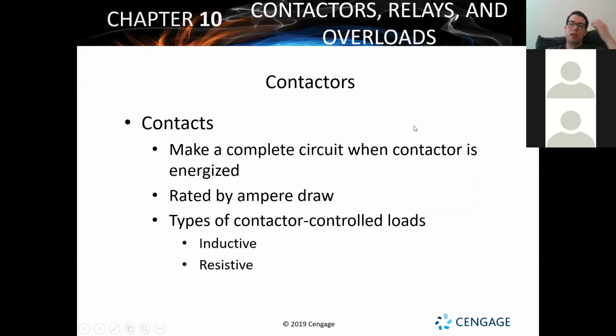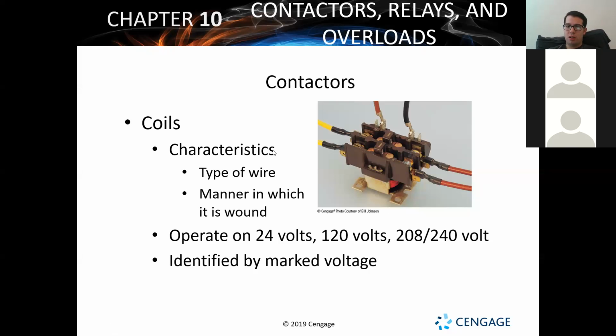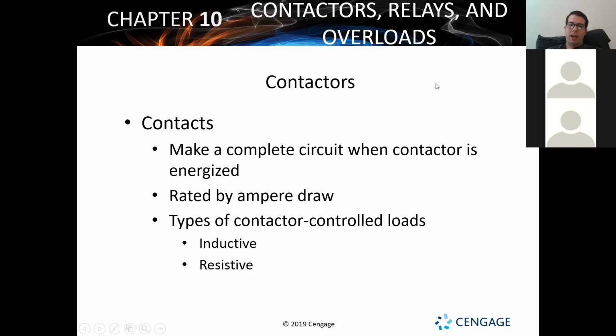So again, the contacts, that's what we were looking at right here on the ends of the contactor. You've got your contacts, and that's what's going to allow for power to be coming in and going out. Now, checking your voltage on your contacts is important. When it's an outdoor unit, you're going to have your power coming into an outdoor disconnect box. Out of that disconnect box, it's going to go right into the bottom of the contactor. That's the next spot it goes.